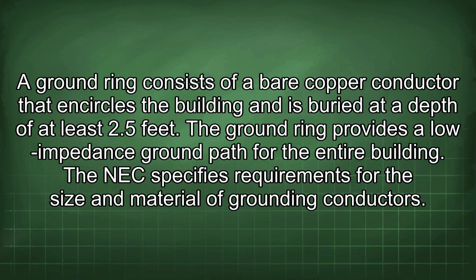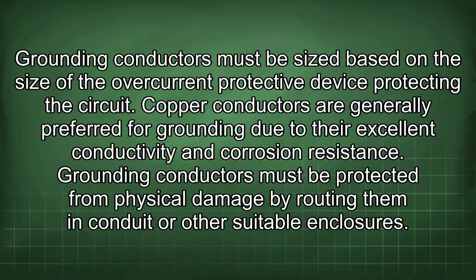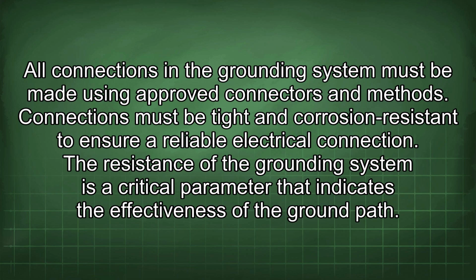The NEC specifies requirements for the size and material of grounding conductors. Grounding conductors must be sized based on the size of the overcurrent protective device protecting the circuit. Copper conductors are generally preferred for grounding due to their excellent conductivity and corrosion resistance. Grounding conductors must be protected from physical damage by routing them in conduit or other suitable enclosures. All connections in the grounding system must be made using approved connectors and methods. Connections must be tight and corrosion resistant to ensure a reliable electrical connection.